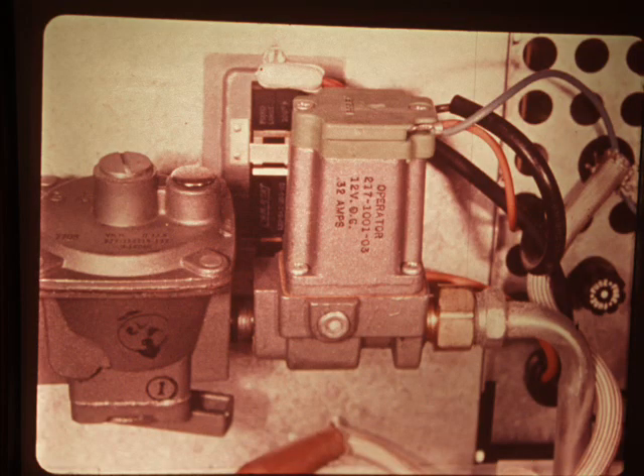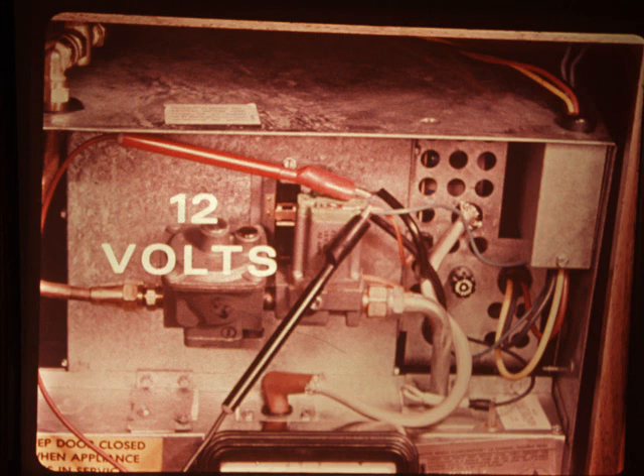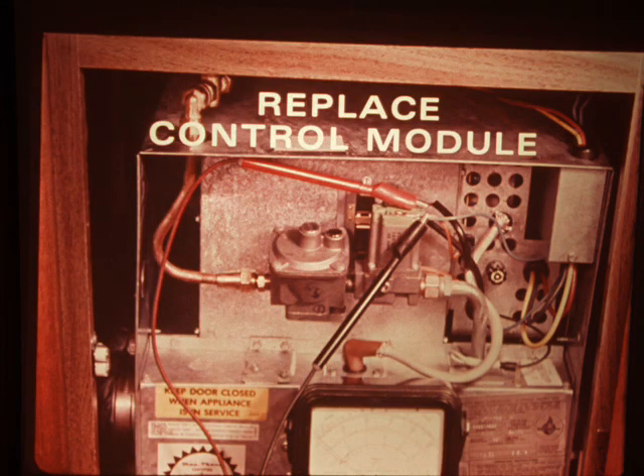If you get a spark at the igniter, but no flame is established, you've got to assume that gas is not reaching the burners through the solenoid valve. Check for voltage to the valve during the startup cycle. If you have 12 volts to the valve and it doesn't open, replace the valve. If there's no voltage to the valve, try operating the furnace with a new control module.